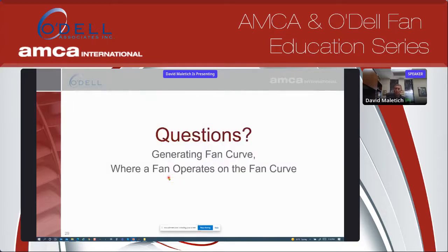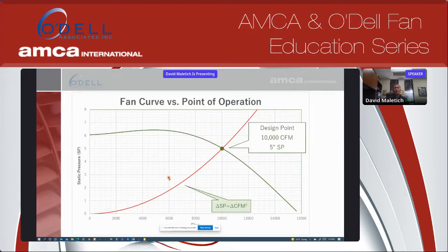And then where the fan is going to operate is the intersection between the system curve and the fan curve, at that point only. If you open up a register, the system curve is going to shift to the right, in this direction here. If you close a register, or filters get dirty, or you close off a branch, the system curve is going to shift up the fan curve. When you do those things, you'll notice it changes the system curve, but it does not change the fan curve.